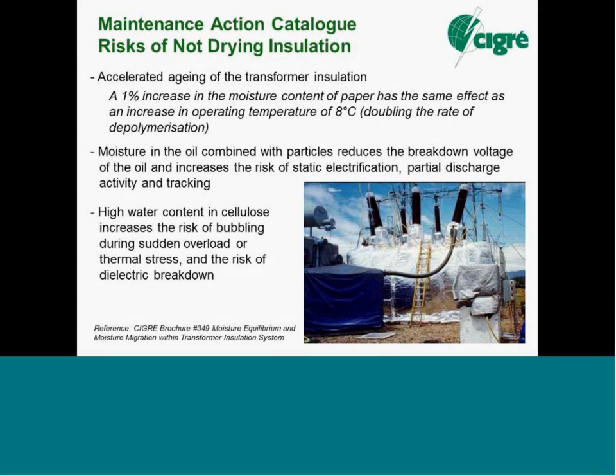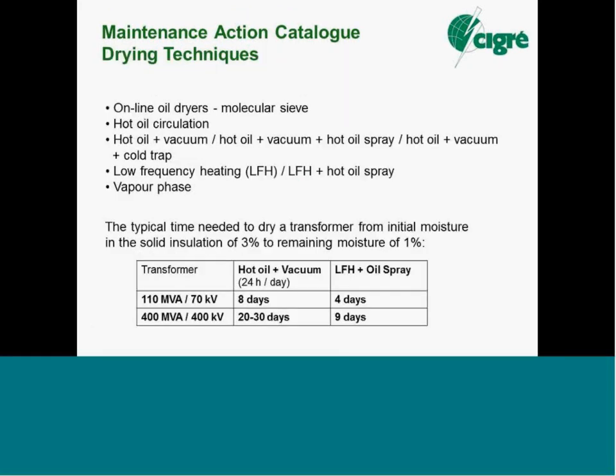We now have the alternative of online oil drying, but that would only slowly dry a transformer, and we see some comparisons of different drying techniques in the next slide. Online oil dryers, the molecular sieve, what I'm referring to, is useful for moderate or low moisture problems. When over 3% moisture in the paper, we should consider the need for an on-site dryer, because we need to quickly and efficiently dry the transformer. The molecular sieve, the online dryer, is a very slow process.